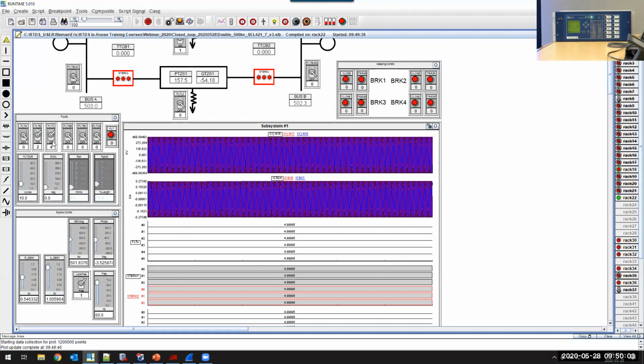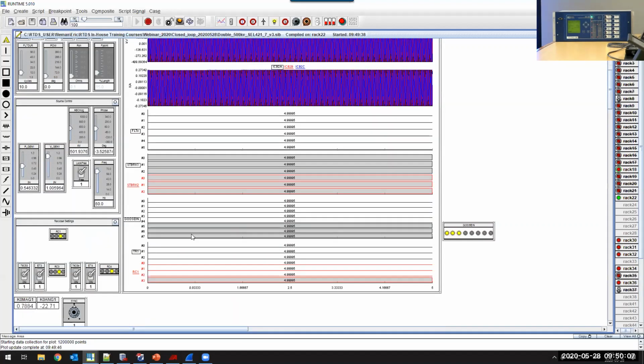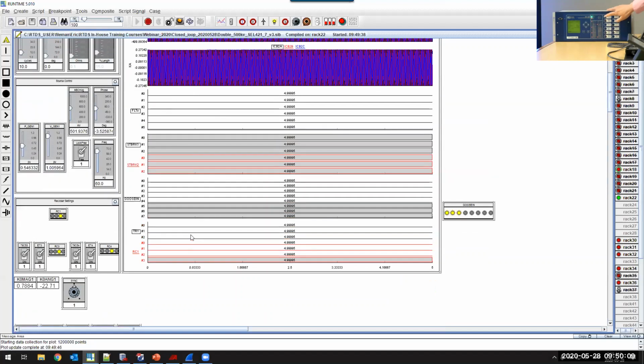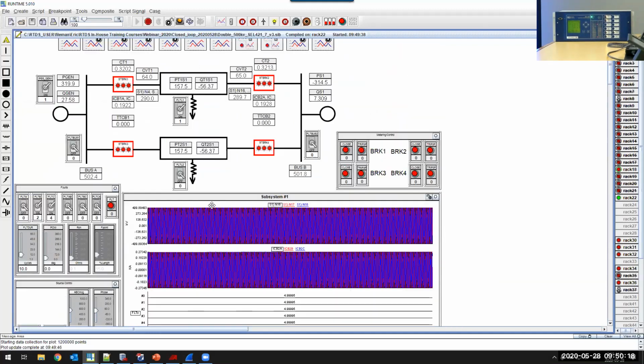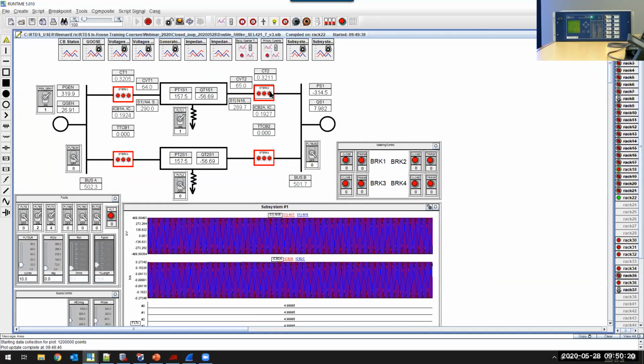And then let's do a different fault, BC to ground. Let's try that. Okay, let's clear the target here and have a fresh view. The relay is back to normal, reset already. What we expect the relay to operate is all 3 phases will be opened and then reclosed.